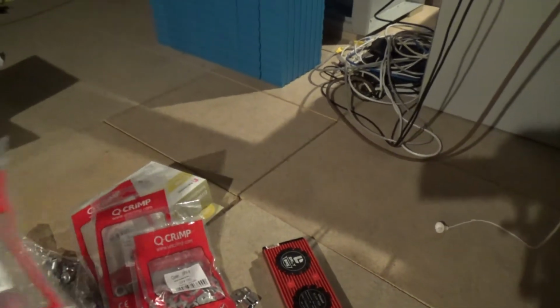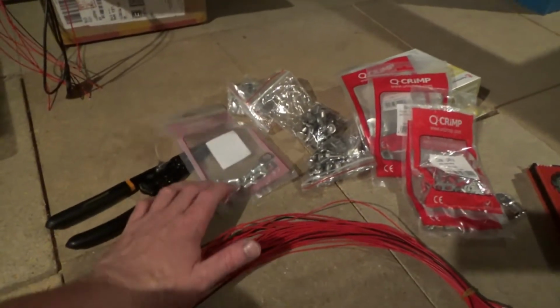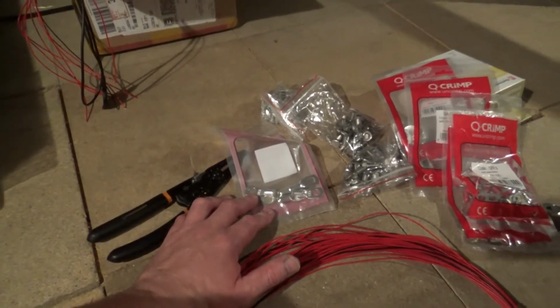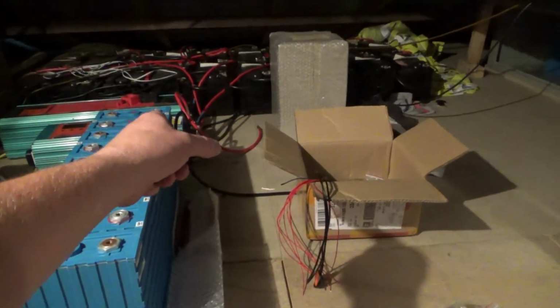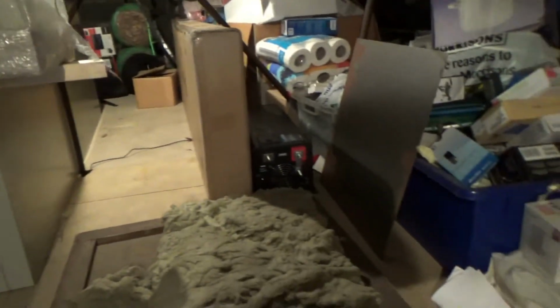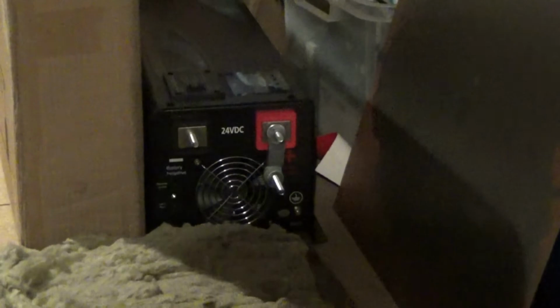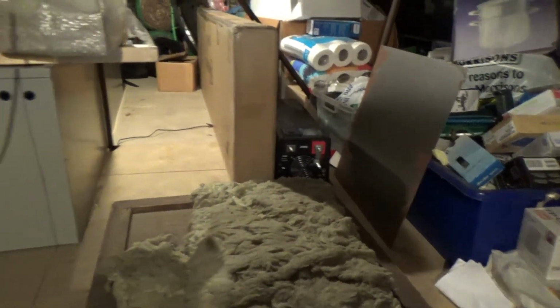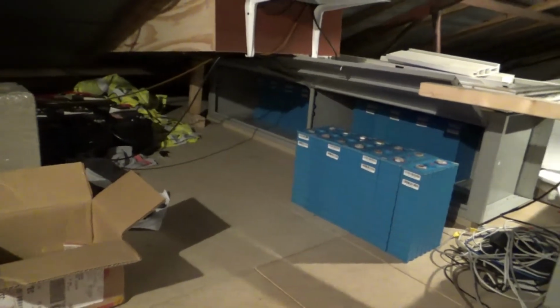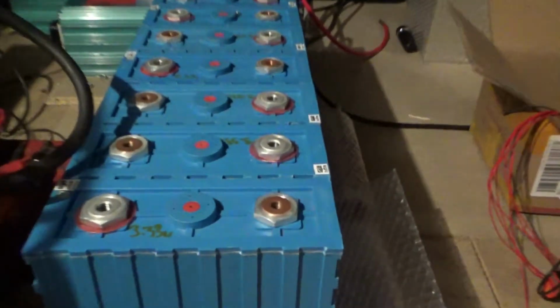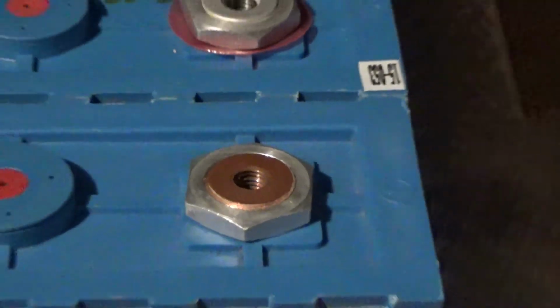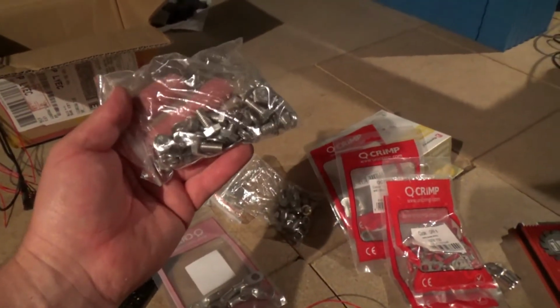I just went down and got 10 M10s to crimp onto the end of my wires. So the wires coming down from the battery to the inverter, the inverters run M10, like this inverter over here, got M10 hardware connections at the back there, and the drop-down thing is a mega fuse. Now the batteries here, that's an M8 hole, 8mm thread, and that's the nuts and bolts they give you. Everything's M8.